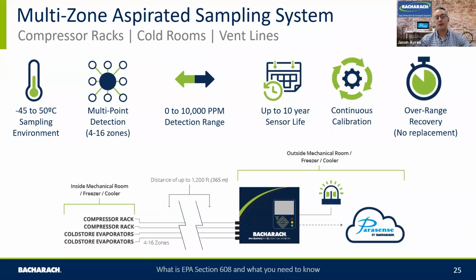And with other technologies that are non-infrared, they can get depleted and affect their sensitivity when they're exposed to refrigerants or other gases in the area. Using an infrared technology mitigates all of that. So you've got a technology that's going to be stable and accurate for years and years. And with any of that technology in the Bacharach multi-zone, the deployment of it is key. The annunciation and connecting it to local systems, beacon sounders and local BMS systems is important, but also then connecting it to an IoT platform, elevating that data out the back of that, using that data to respond and be more proactive in responding to leaks.